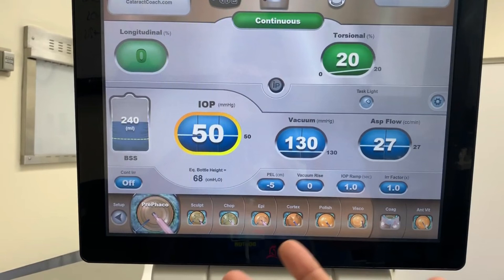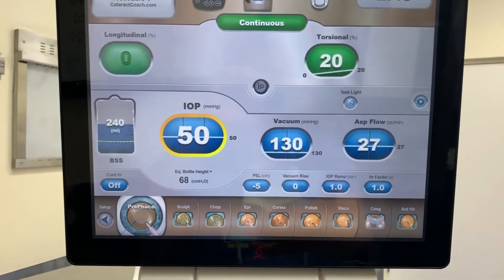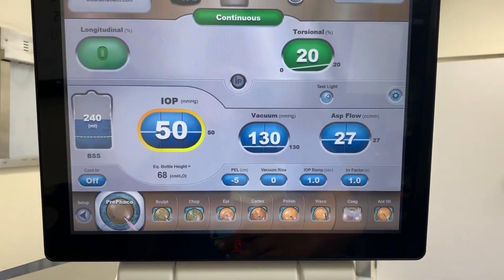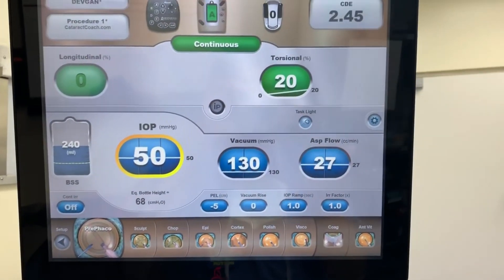Third is aspiration flow. The aspiration flow pulls material toward the phaco tip and the ultrasound movement of the phaco tip pushes material away. Vacuum holds nuclear fragments on the phaco tip. Surgeons can optimize their settings to improve this balance. Generally, low flow slows down intraocular events, while high flow speeds them up.